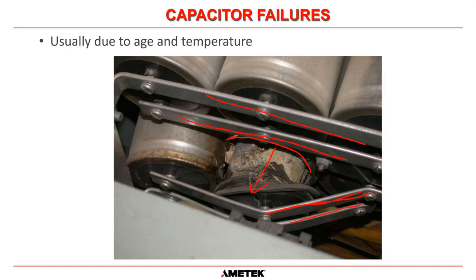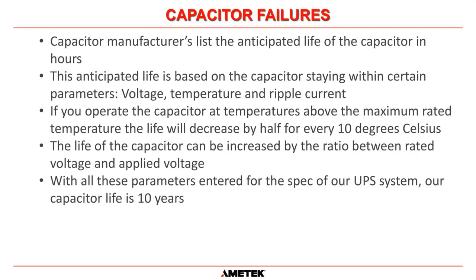So it's a very significant event when an electrolytic DC capacitor lets go and fails. And there would have been a lot of smoke involved with this failure as well. You can see there's a lot of electrolyte debris around the failed capacitor as well. So we really want to be able to prevent this, okay? And the capacitor manufacturers, every capacitor manufacturer in the world lists the anticipated life of their capacitor in hours, okay? And that life is based on the capacitor staying within certain parameters, and that's voltage, temperature, and ripple current. So the capacitor manufacturer will say you must stay within, let's say, less than 105 degrees Celsius, and you will get a certain amount of hours at that temperature range with the voltage within tolerance and the ripple within tolerance.